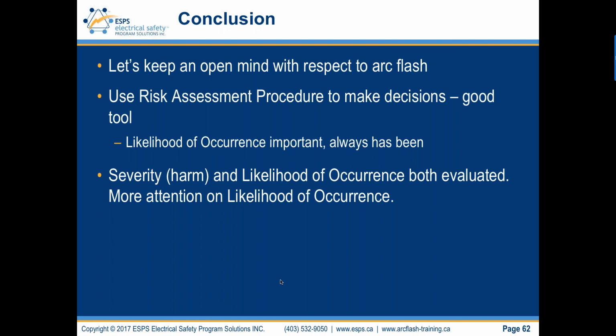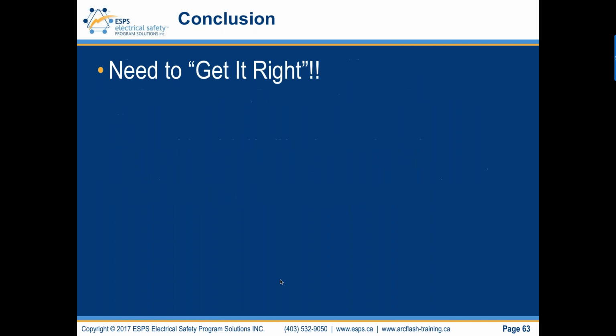Severity of harm and likelihood of occurrence are both evaluated in the risk assessment procedure, as I just said. More attention on likelihood of occurrence. We need to get this right, or as right as we can get it. So arcing fault and arc flash, we need a lot of work yet, and I think we've gone down a path and we need to walk back up that path and get back to where we were specific to operating energized electrical equipment.